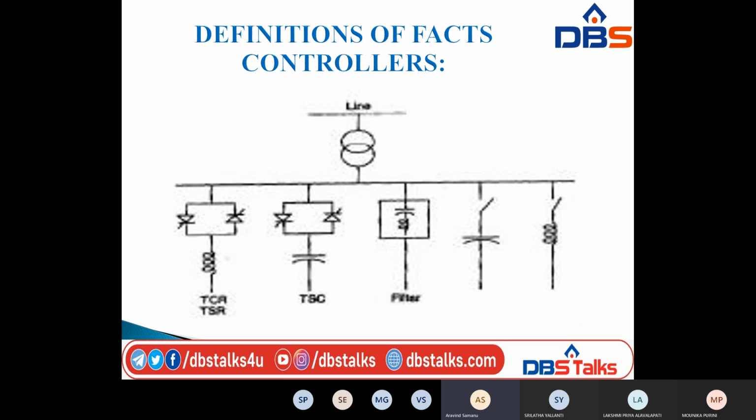Next one is the thyristor switched reactor. Both are similar. Here it is also a shunt connected controller, using a thyristor switched inductor whose effective reactance is varied in a stepwise manner. In the previous case, the thyristor controlled reactor, the effective reactance is varied in a continuous manner by partial conduction control of the thyristor valve.